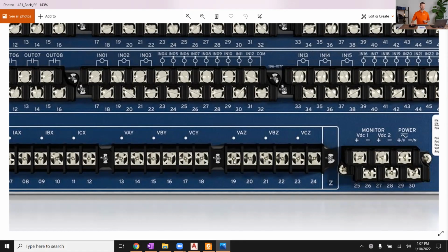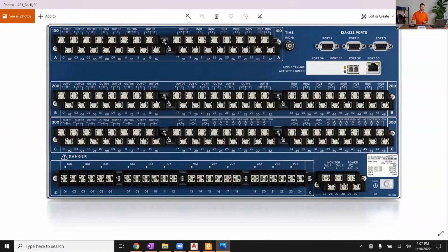We talked about that in the auto reclosing challenge, if you want to learn more about sync check. But there are applications where you need more than just a single three-phase PT set wired into the back of your relay. Sync volt check, I should say. But this is the relay side of things, very similar to what we drew up on the CTs. You want the PT secondary polarity dot to be wired to the relay voltage polarity dot, just like we drew up on the CTs. That's kind of our conventional norm.